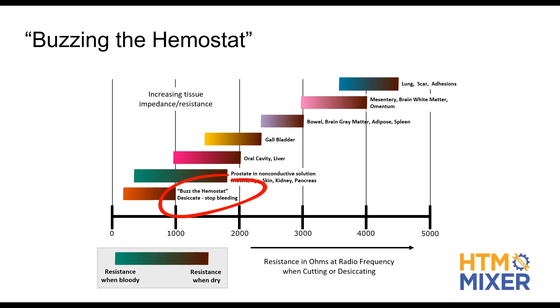And then they take the pencil and bring it over to the forceps they're using. We say you're not supposed to do that, but the surgeons don't listen to us anyway because they know it works. But I give two precautions to the biomeds. One, they better not be keying it before they get there, because if they do, they'll get an arc jumping from the electrode to the forceps. You also get some capacitive coupling, which is why they burn it through the gloves. The second thing is, if they're going to do that, tell them to hold on to it with more area — the more area, the better. If you're afraid of that thing and only use a little bit, you create a high concentration area. So we caution them both ways: don't do it, but if they do, here's how to do it safer.